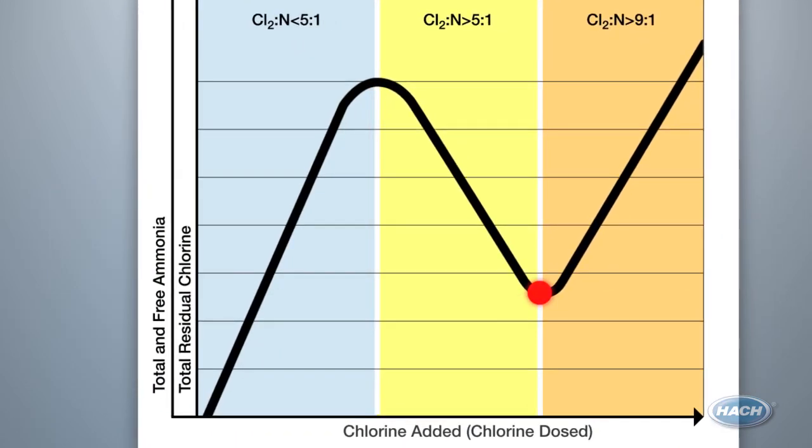Once you pass the point where you have fully bonded all the nitrogen from the ammonia with the chlorine, you return to the original chlorine curve, where for every part of chlorine you dose, you will see one part of chlorine residual.